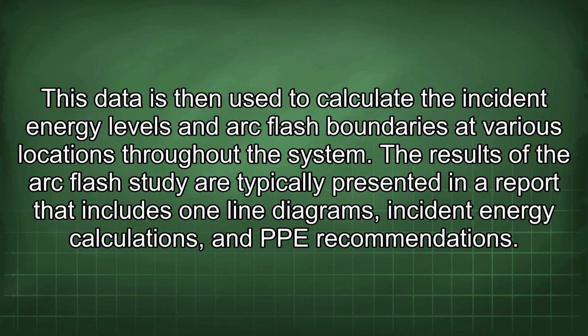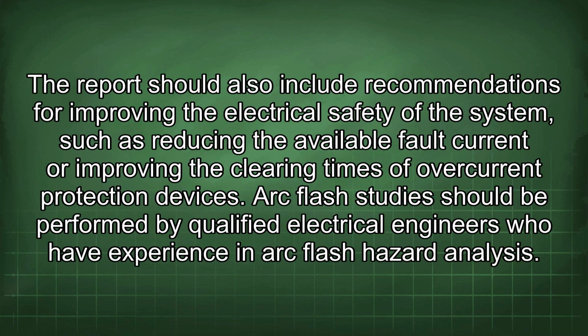This data is then used to calculate the incident energy levels and arc flash boundaries at various locations throughout the system. The results of the arc flash study are typically presented in a report that includes one-line diagrams, incident energy calculations, and PPE recommendations. The report should also include recommendations for improving the electrical safety of the system, such as reducing the available fault current or improving the clearing times of overcurrent protection devices.